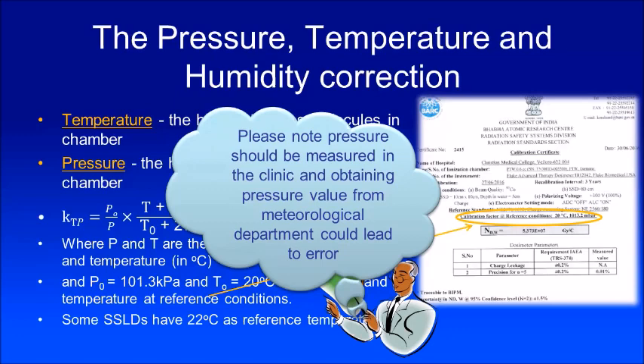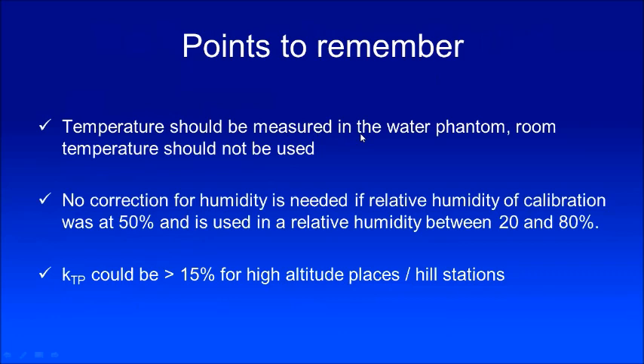Points to remember: temperature should be measured in the water phantom — room temperature should not be used. No correction for humidity is needed if the relative humidity at calibration was 50% and your room is between 20 and 80%. The temperature-pressure correction could be as high as 15% for high altitudes and hill stations.